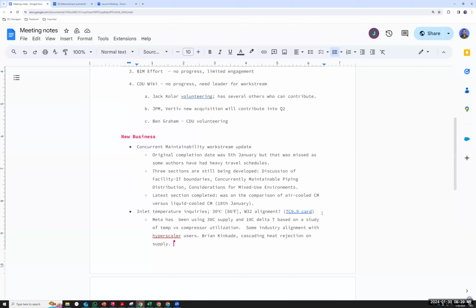Yeah, because the CDU itself isn't going to require 100% flow through the heat exchanger—it's going to modulate and vary all the way from, who knows, 10% to 100% of capacity, depending on the jobs run on the IT. So you'll want to tend to utilize some of that mixing characteristic, possibly using a three-way valve or a bypass.